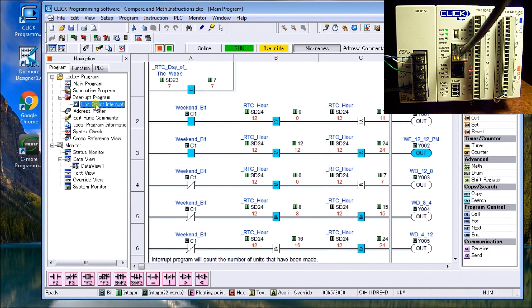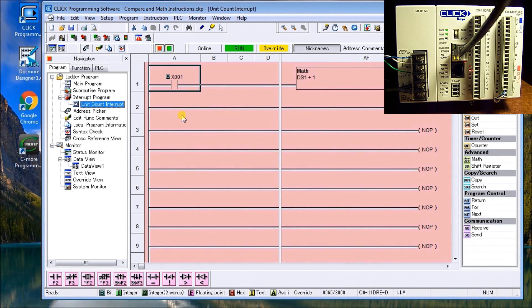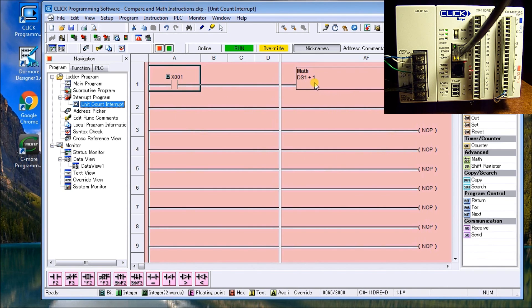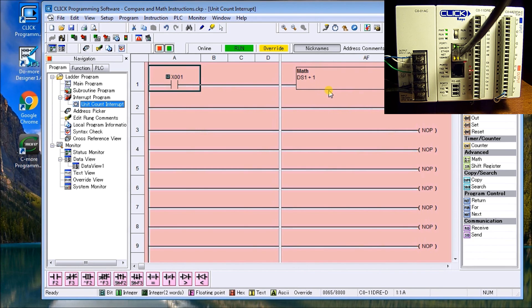And if I double click my unit count interrupt, this is my interrupt routine. So you'll notice I have to have my X one on. And then what we'll do, it will add one to the memory location DS one, and it will store it at DS one. So all this is doing is actually giving me a account value. It keeps incrementing.